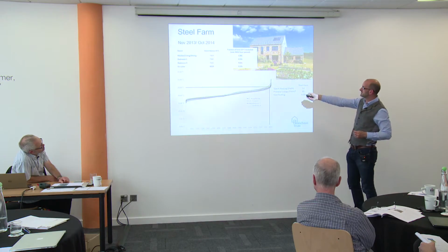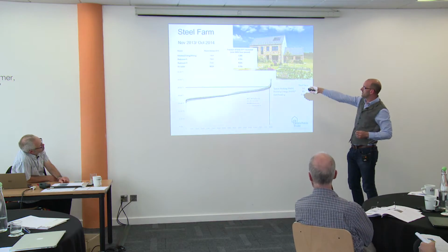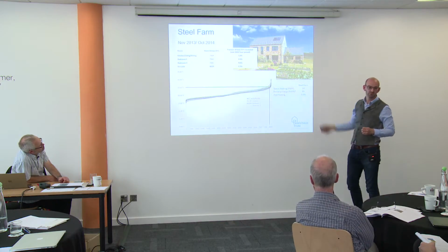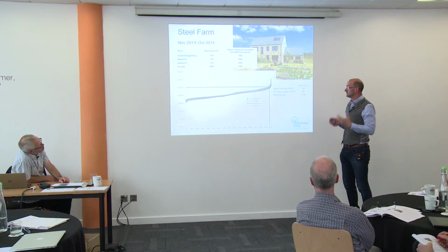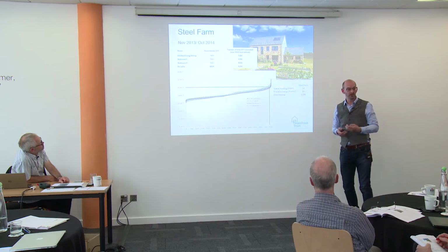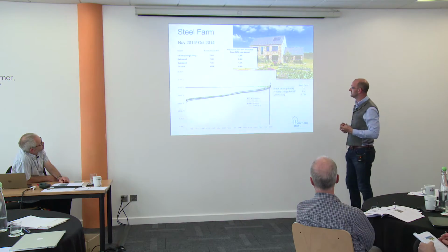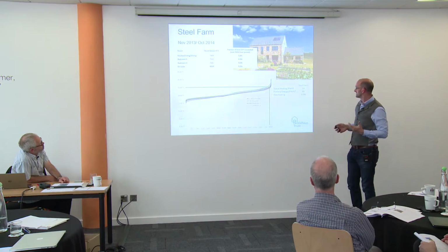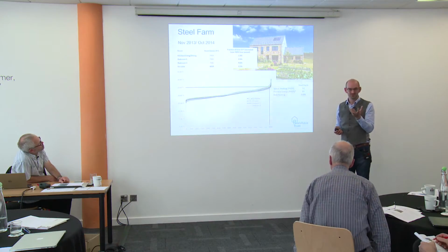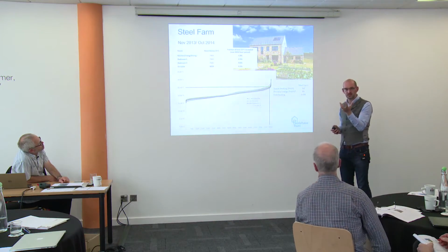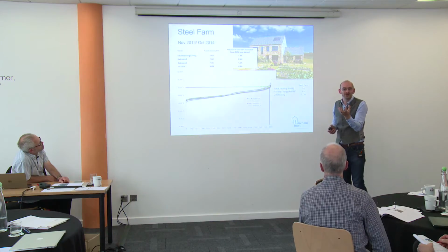The client's bedroom at the back of the house went over 21 degrees Celsius for 0.9% of the year. So that's a north facade. So all in all, a success. A very comfortable place to live. So basically, PHPP works, but it kind of assumes you're in an idyllic location.